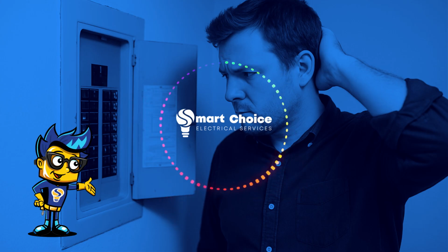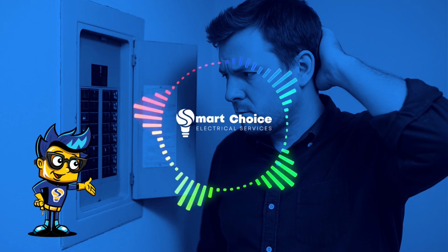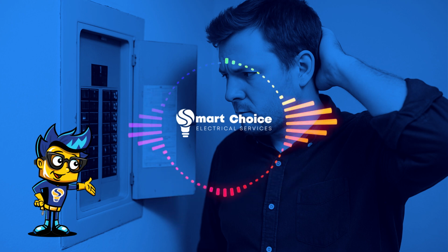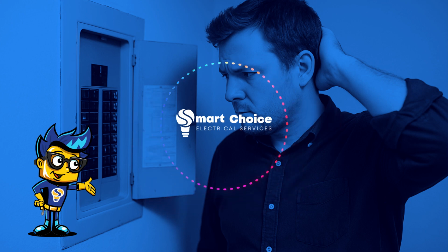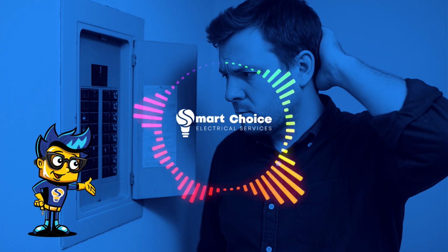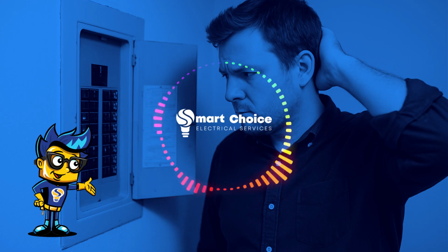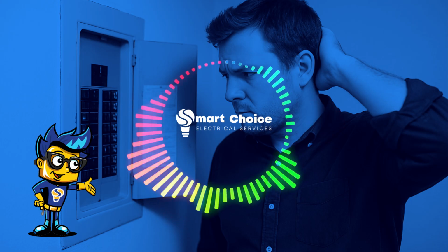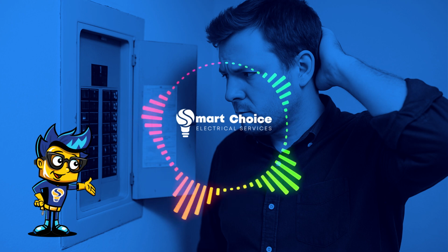So what's usually going on when breakers trip constantly? Most often, it means your panel is overloaded, struggling to handle the amount of electricity you're asking it to deliver. Or it could be a faulty breaker itself, they wear out, or sometimes deeper issues like problems with the wiring in your house. This is more common in older Houston homes, built before we had ten devices charging in every room. Those older panels, installed decades ago, just weren't designed for today's high energy demands, think computers, big TVs, smart home stuff, EV chargers.